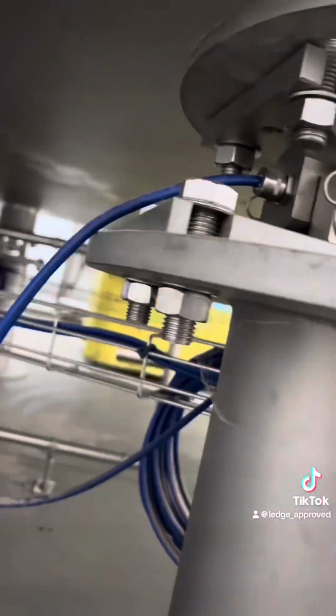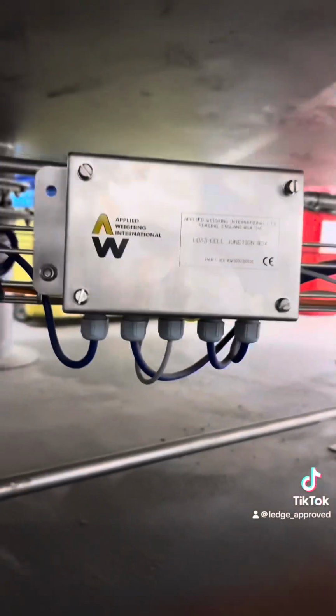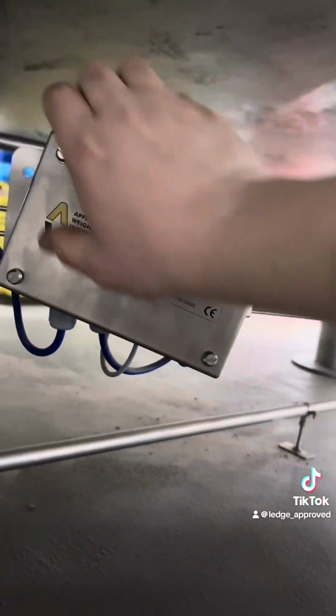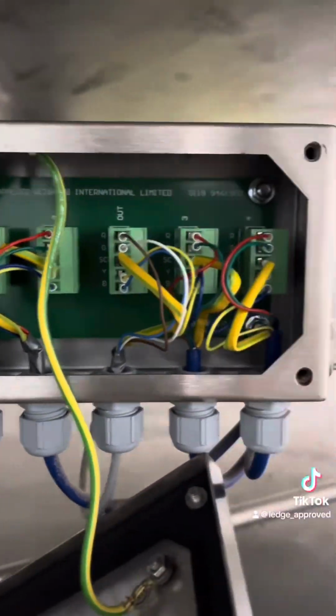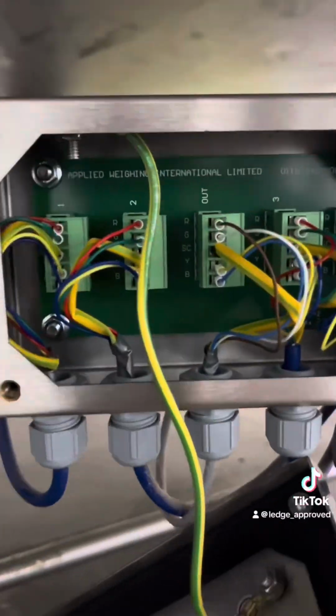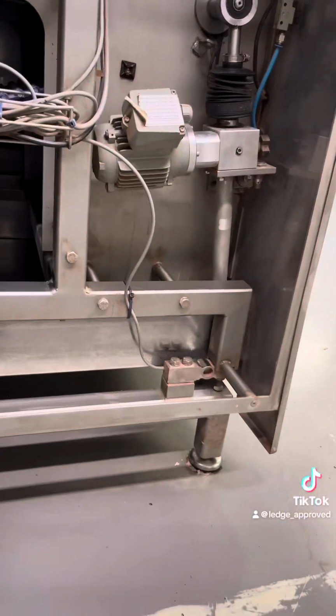What we're looking at is electronic load cells. Shear beam is the most common we've got in our factory, but there are many different types. Saying that, they all work the same principle, schematics, and the way of testing is just the same, just different applications. And here you can see the junction box with all four going back and one signal going out to the PLC or your receiver.